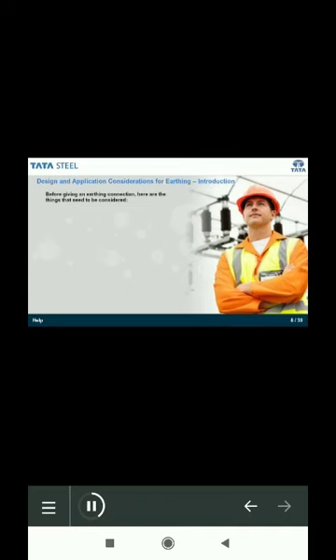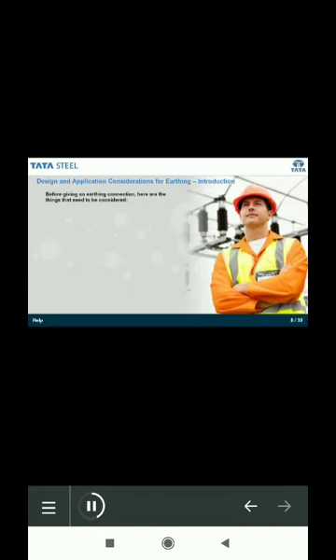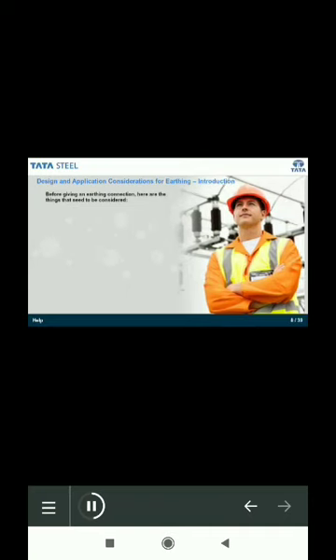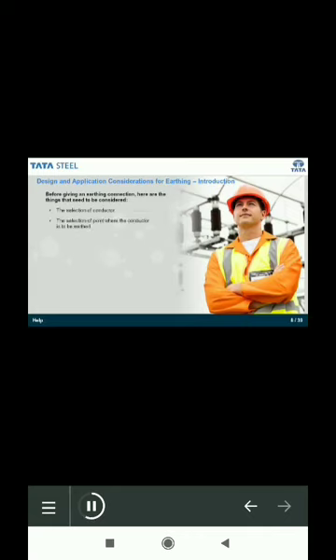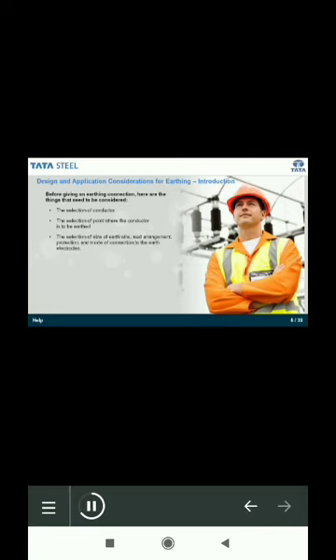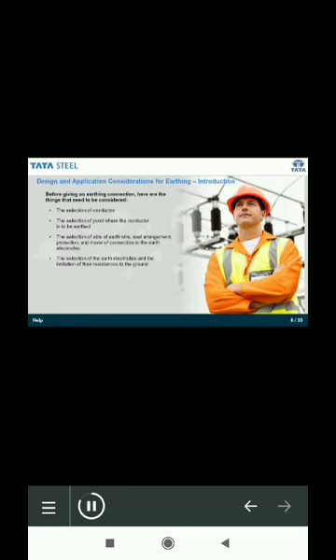Once you decide that an earthing connection has to be given, these are the points that need to be considered: the selection of conductor, the selection of point where the conductor is to be earthed, the selection of size of earth wire, lead arrangement, protection and mode of connection to the earth electrodes, the selection of earth electrodes and the limitation of their resistances to the ground, fault current of the system, and location of earthing station.